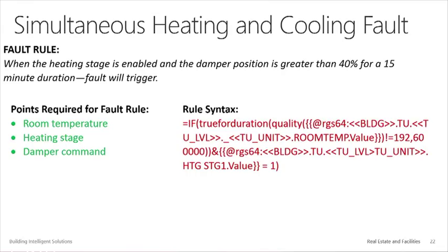Just a few points: room temperature, heating stage, and damper command. This is a syntax, we're not writing code, we're using if-then-else statements. The value is, the person writing our fault rules—we have about 195 of them for 35,000 pieces of equipment—has been out of school with a mechanical engineering degree for 16 months. So it's not complex, it's not IP, it's the ability to create these. We drop these fault rules in the tool and away you go.